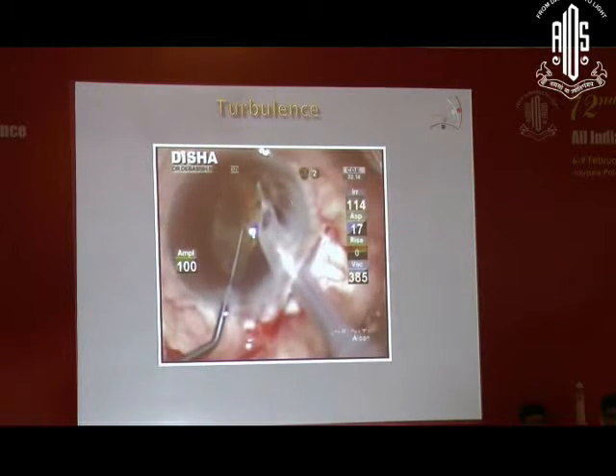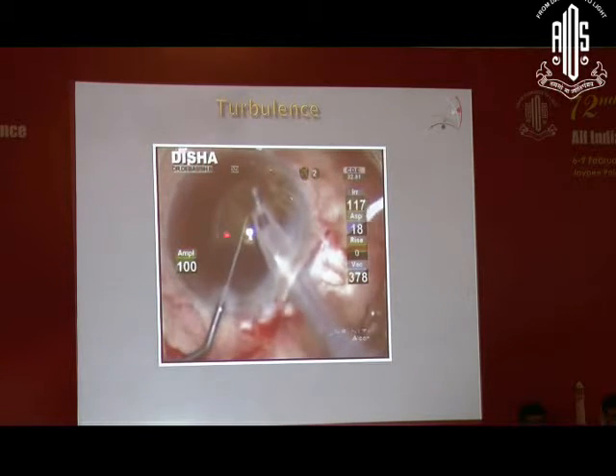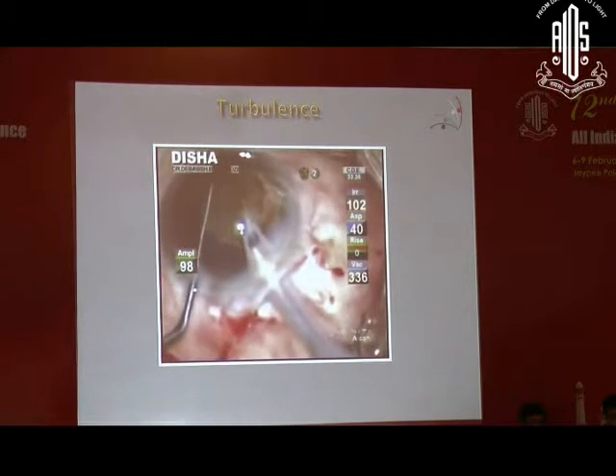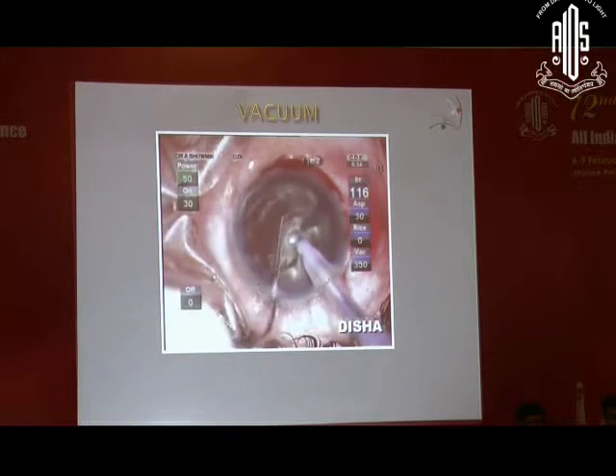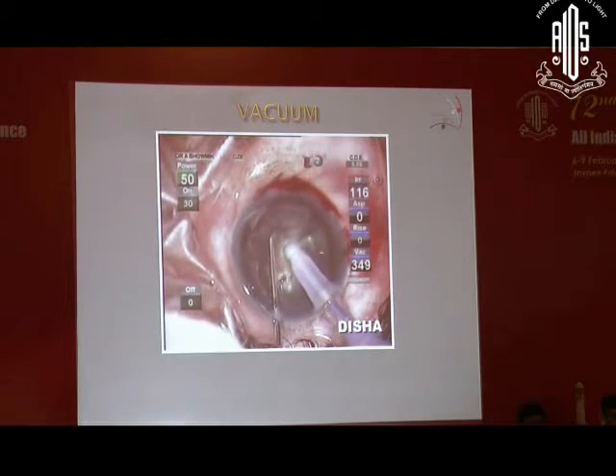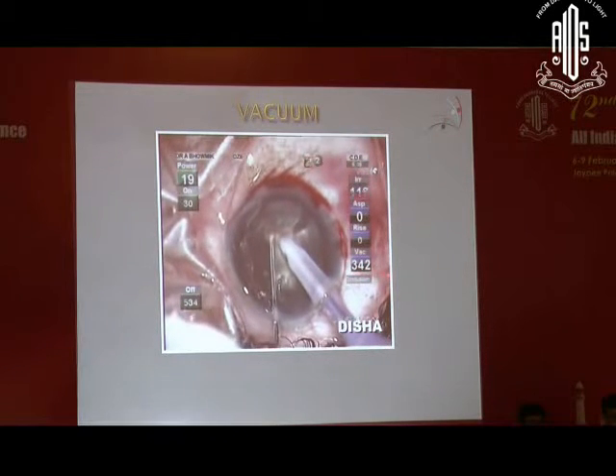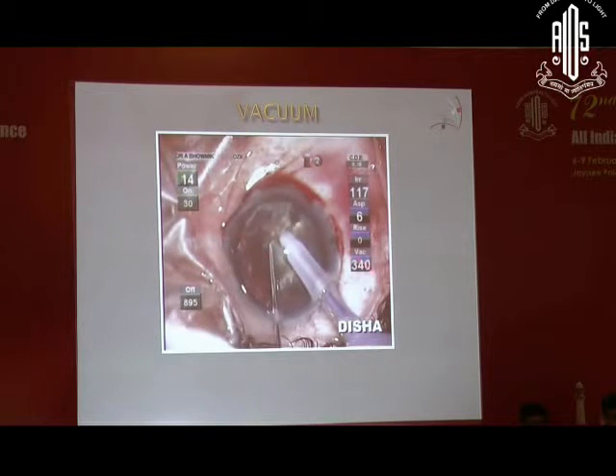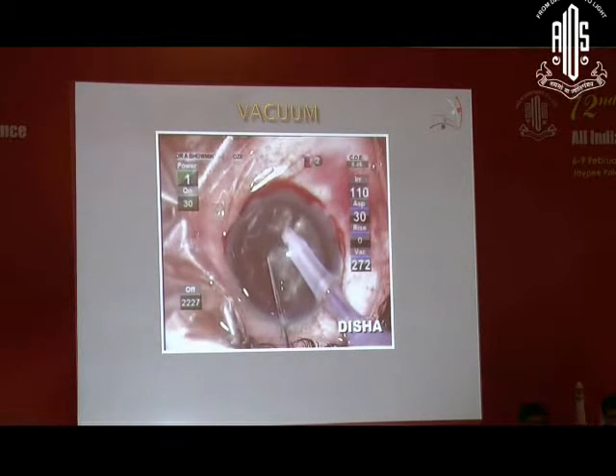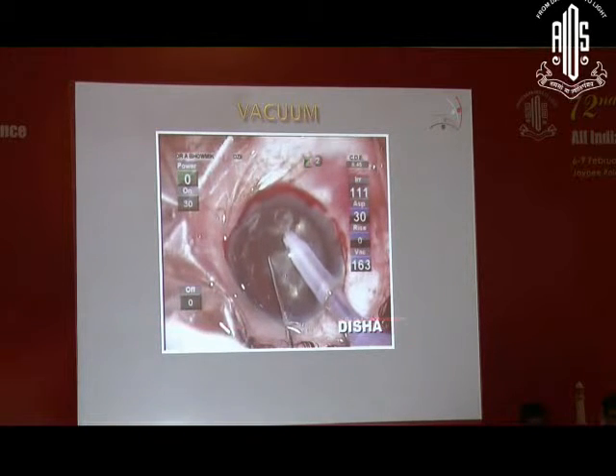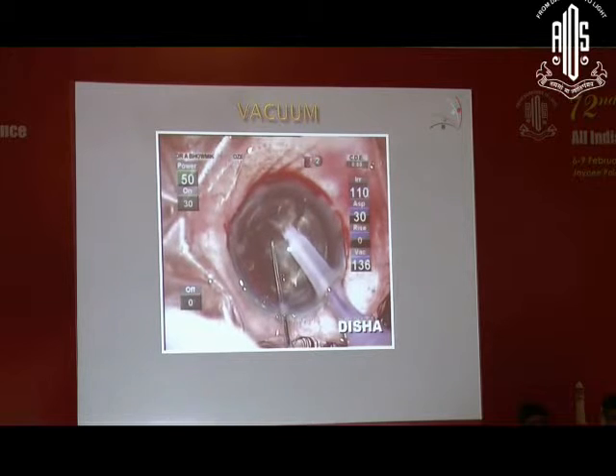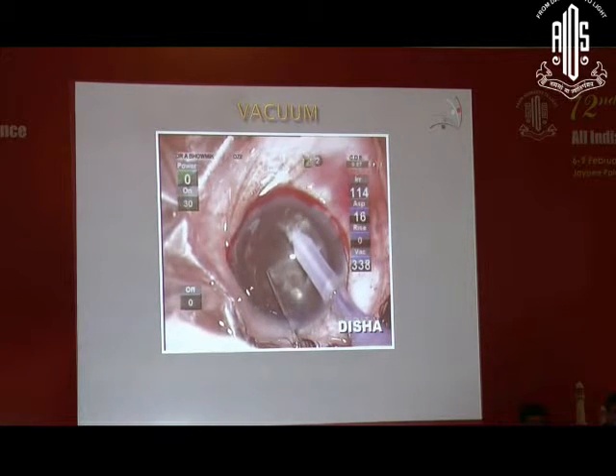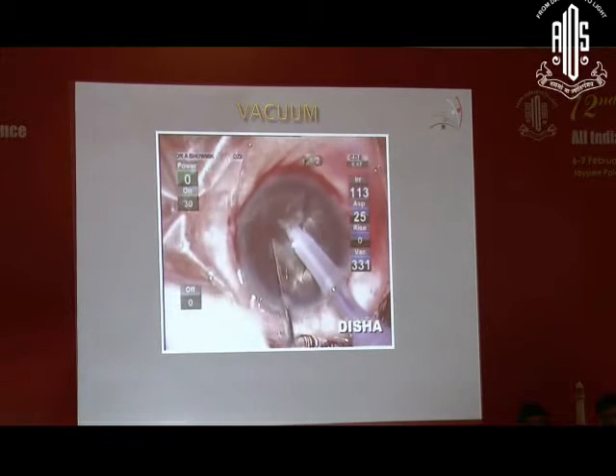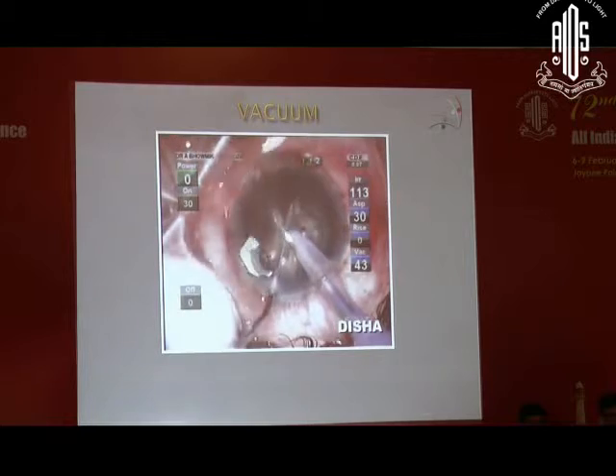This aspiration of course, 60, is not desirable. The downside of having higher aspiration flows is that the fragments cause a lot of turbulence in the eye, which is not good. And now see the vacuum rise here. So there the energy is being used, the vacuum is held and the chop is executed. So the vacuum gives us the hold of the nucleus, the chop. So all through, you see that the vacuum is high. So this is how you hold and then chop.